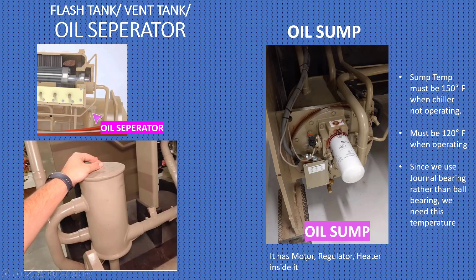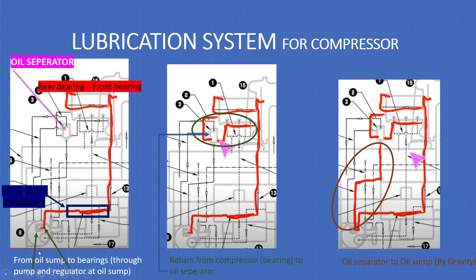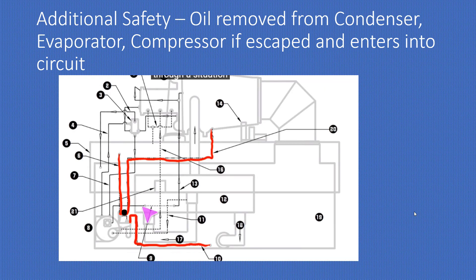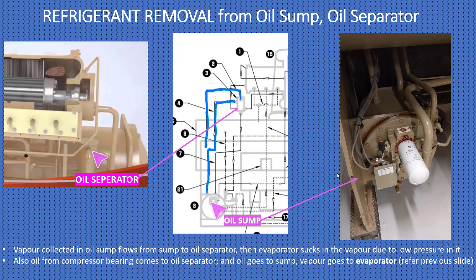The oil sump has a motor, regulator, and heater inside it. Some important key points: oil temperature must be 150°F when the chiller is not operating and 120°F when operating. Since this chiller uses journal bearings rather than ball bearings, this temperature is required for lubrication. The lubrication system for the compressor flows from the oil sump to the bearings through a pump and regulator. Oil returns from the compressor bearings to the oil separator, then back to the oil sump by gravity. An additional safety circuit removes oil that has escaped into the refrigerant circuit from the condenser, evaporator, and compressor.